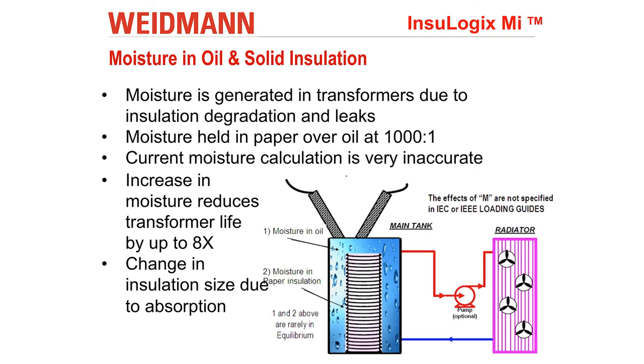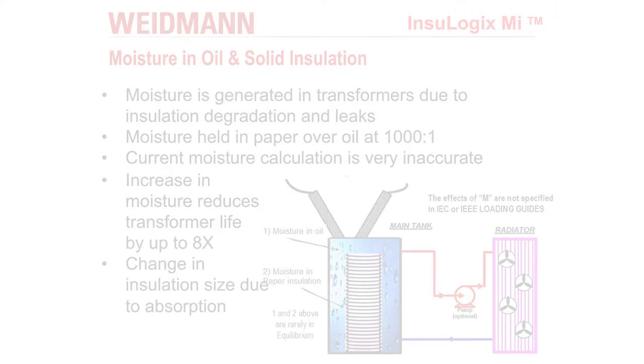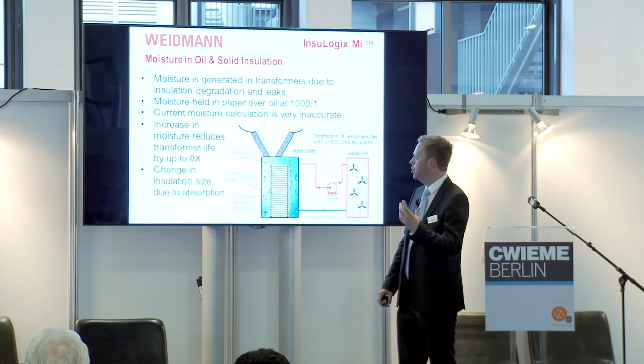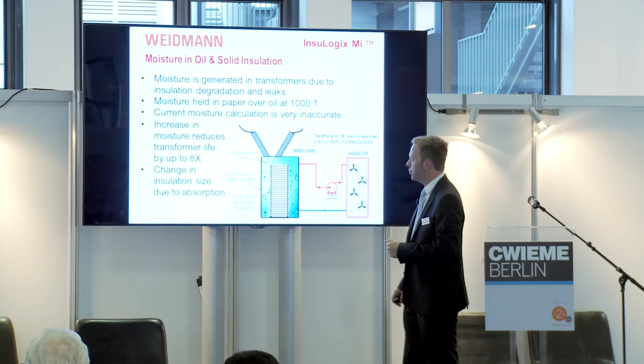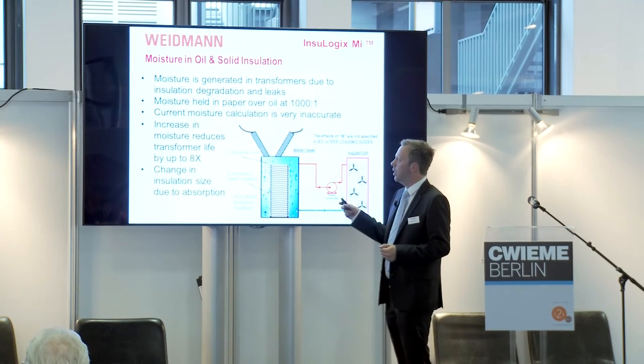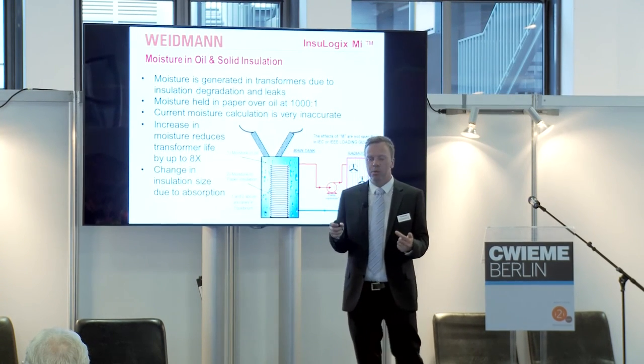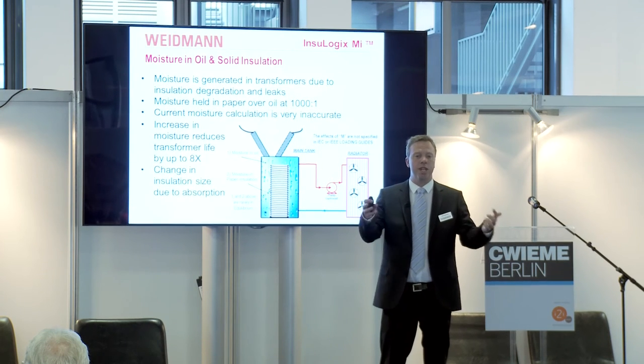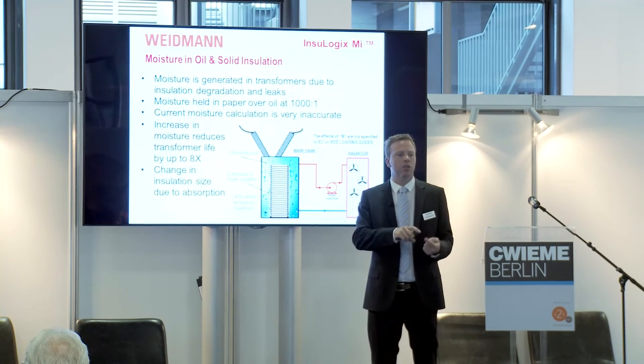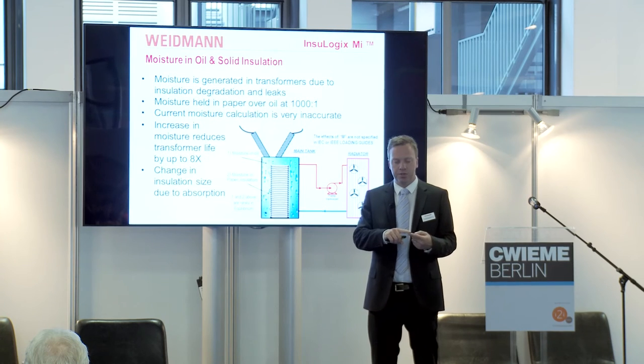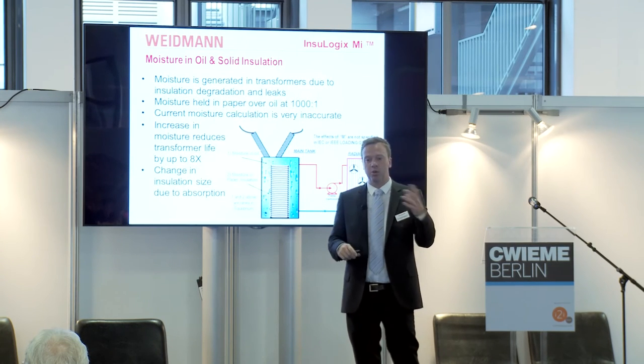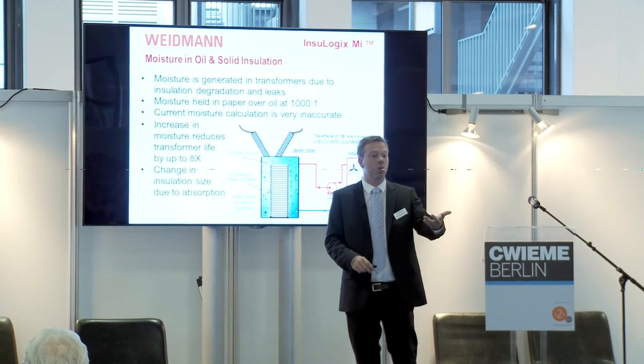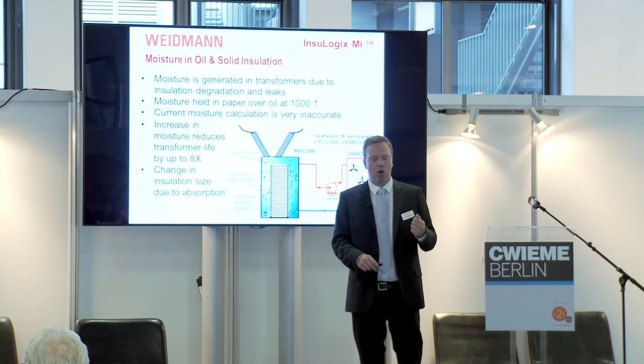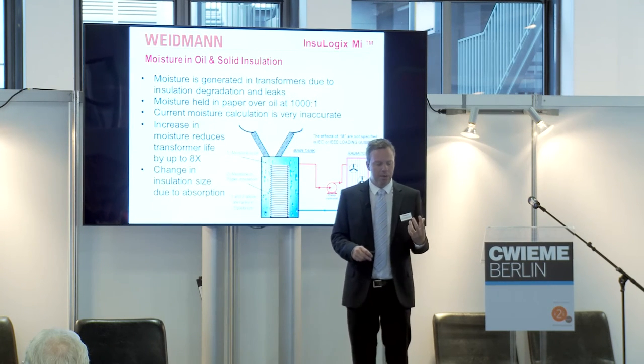Okay, now we're on to the more interesting new development of moisture in oil and solid insulation. As I'm sure you're aware, there are a number of ways that moisture is generated in a transformer. The most common, I guess, is first of all, as cellulose degrades, you get moisture generated in the transformer. Secondly, leaking gaskets.